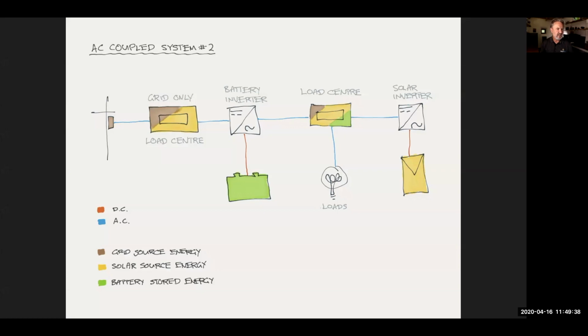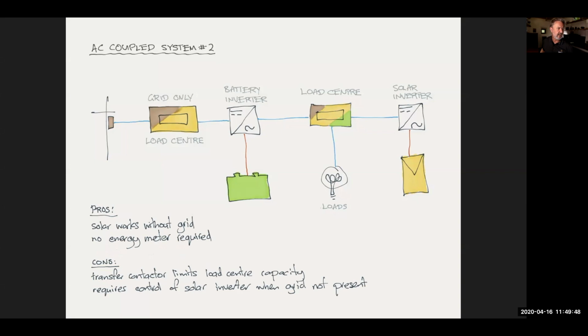So what we're looking at here is that AC coupled system that allows charging to occur via the battery's load port from the solar inverter. I've put the pros and cons here to summarize: the pros are that the solar works without the grid. This is a small benefit if you have only intermittent grid outages, but if you've had outages that last days, it's very annoying to have a solar array on your roof and a battery inverter system that won't charge because it can't couple on the AC side without the grid being present. You'll also note there's no energy meter required in this diagram, because all of the energy we're interested in is passing through the battery inverter, so its internal measurements are used to choose when to charge and discharge.